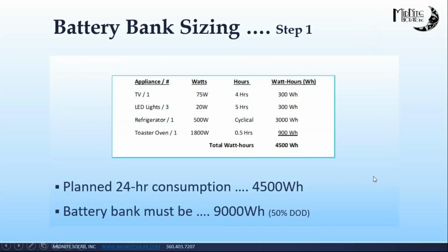From the last session's load analysis, we added up that we need 4,500 watt hours of stored energy. If you're going with flooded or sealed batteries — we'll talk about those later — on average, almost all of them want you to draw those batteries down no less, or no more, than 50%. So you start with a full tank of gas, 100%, consume it, draw it down to 50%, and that's it.